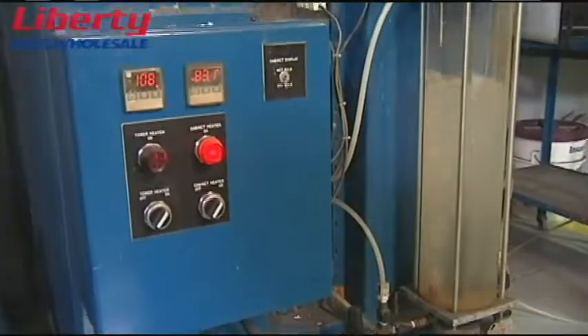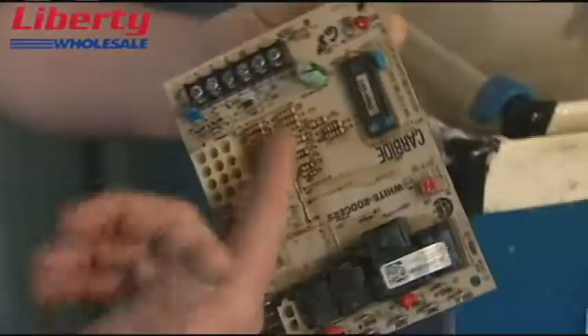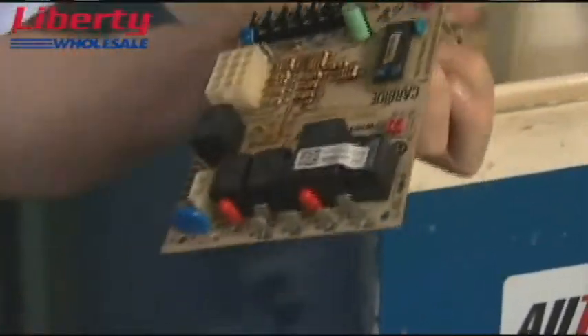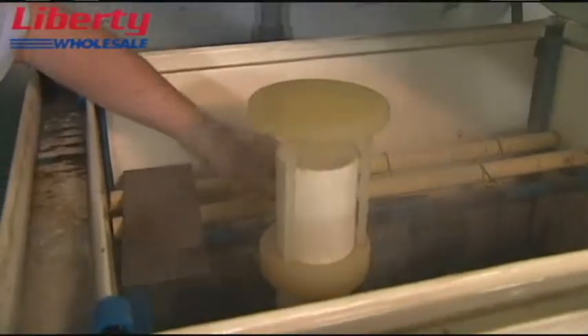I'd love to see some of this. Why don't we head out and take a look at the salt fog chamber. This is the salt fog chamber — it's a way of really driving a corrosion reaction. What you'll see here is it's starting to develop some corrosion. What we're looking for is how good is the conformal coating on the board, how well are the components standing up, and are we getting ingress of the salt fog under the relays, those types of things. Every day we'll take this component out, rinse it with deionized water, dry it, and put it back in a unit and make sure it's operating. That's the way we do the test with this.